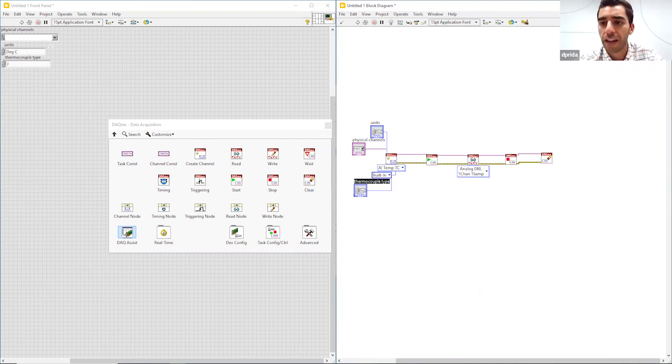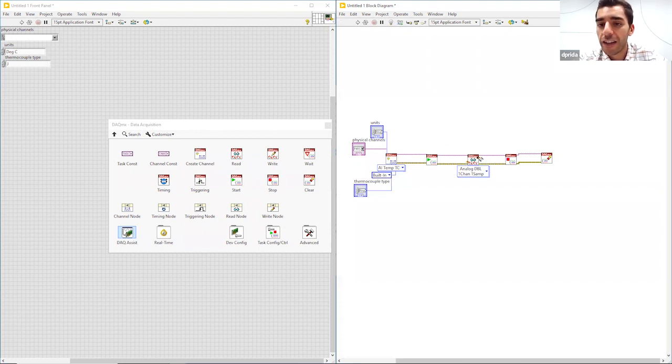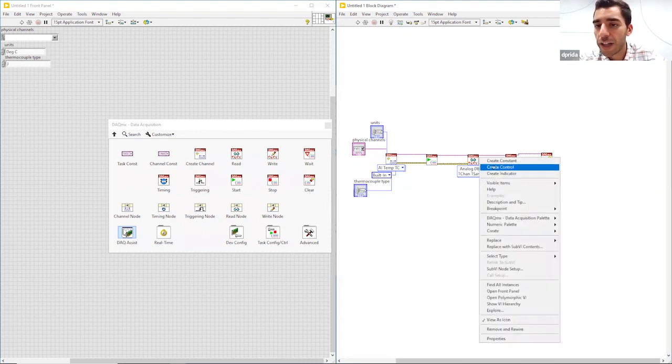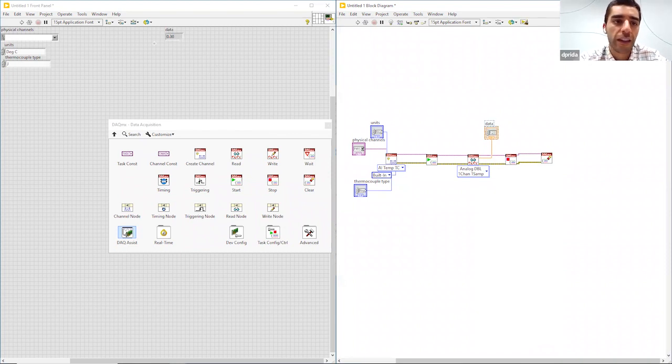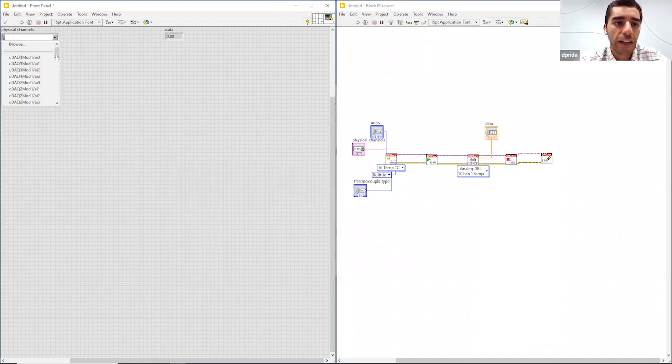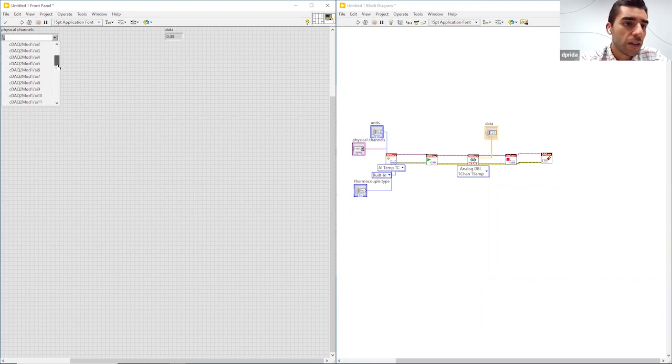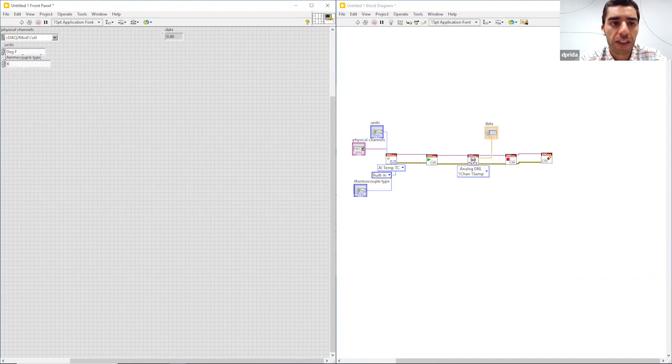I also want to be able to see the data that we're going to be taking, so I'm going to go ahead and create an indicator and that also appeared right here on the front panel. I'm going to go ahead and select the channel and I'll input zero. I'm going to change the units to Fahrenheit and the thermocouple type to K.